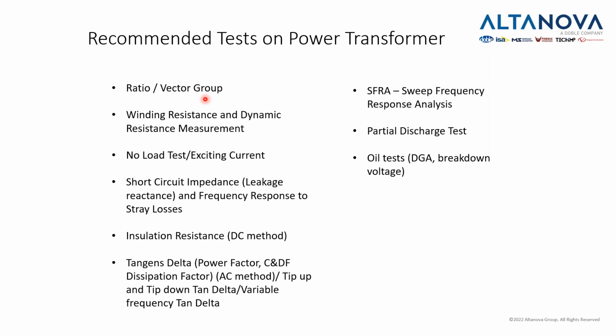Ratio and vector group. We will talk about winding resistance and dynamic resistance. We will talk about no load, or as they also call it, excitation current, and about short circuit impedance, also known as leakage reactance, and frequency response to stray losses. We will mention insulation resistance using the DC method, and tan delta, also known as power factor, and C&DF, or dissipation factor, and the AC method.